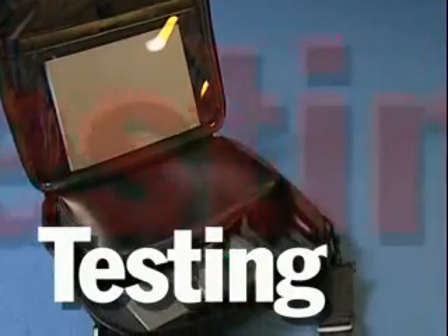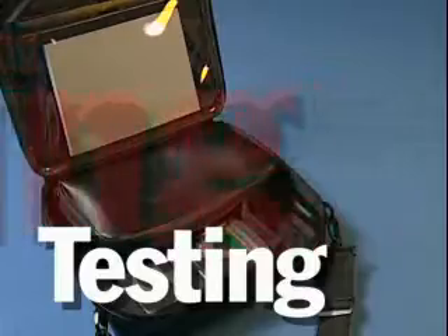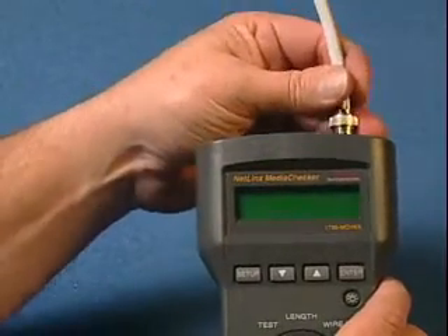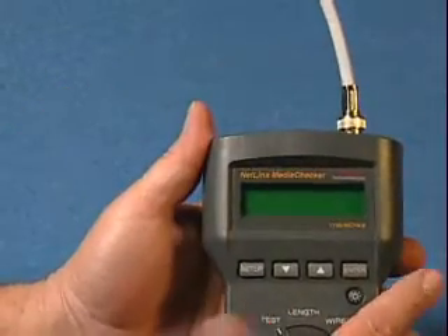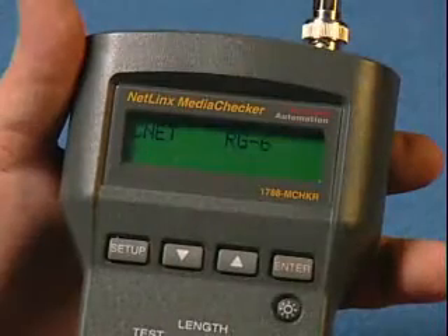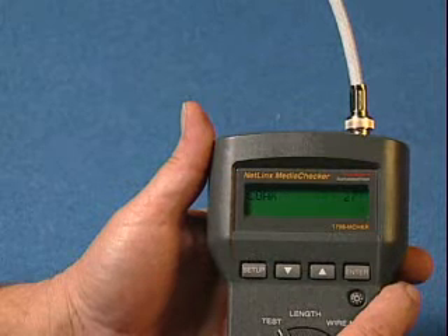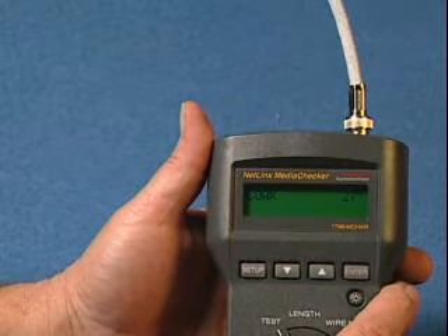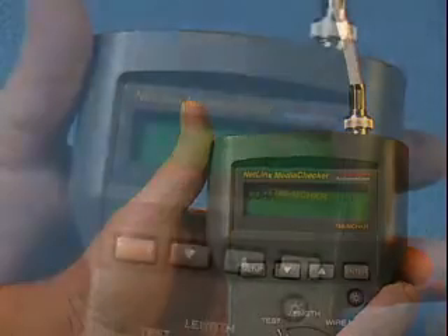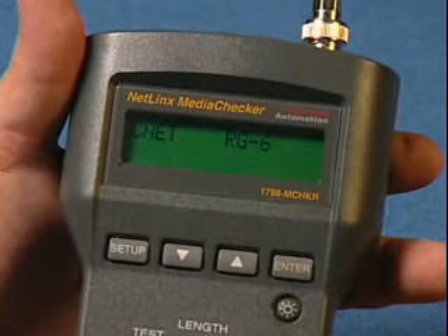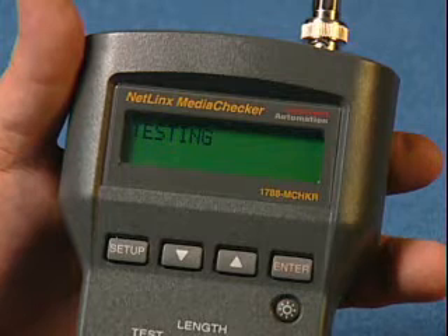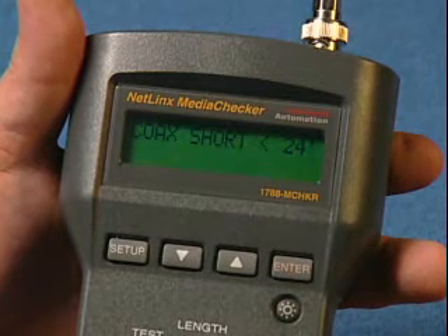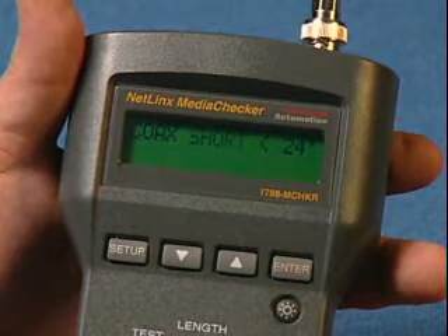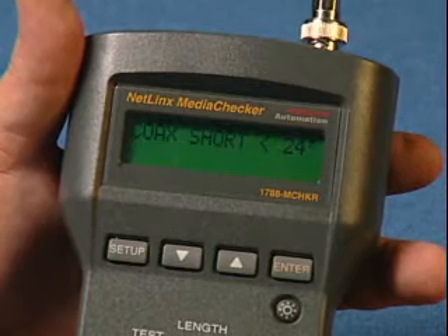The preferred method of testing is to use the Rockwell Automation NetLinx MediaChecker, catalog number 1788MCHKR. Be sure the NetLinx MediaChecker is set up properly for the cable you are testing. Simply attach the cable to the tester and rotate the selector switch to the test position. A single beep indicates a good cable, and a connection with no shorts or opens to the length indicated. A multiple beep indicates a shorted cable or connector. You will need to troubleshoot the link to determine the source of this problem.